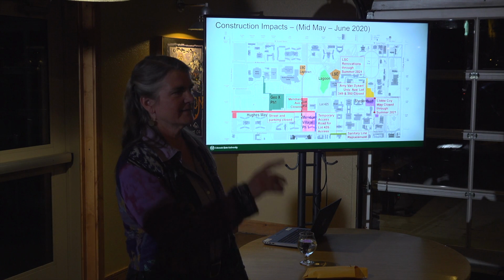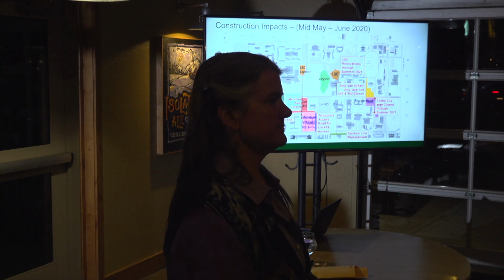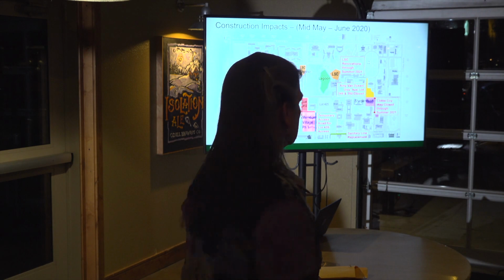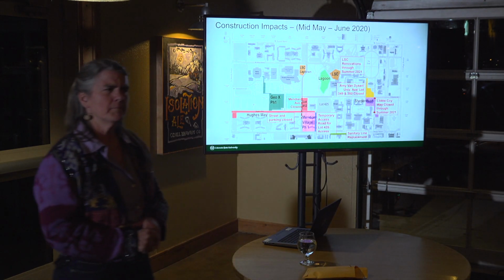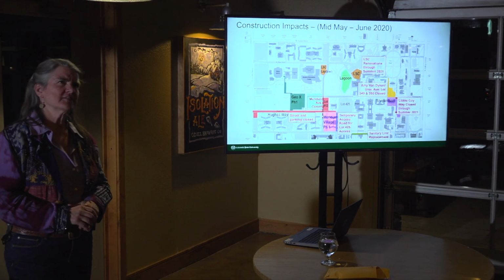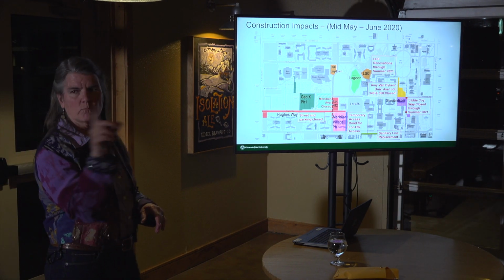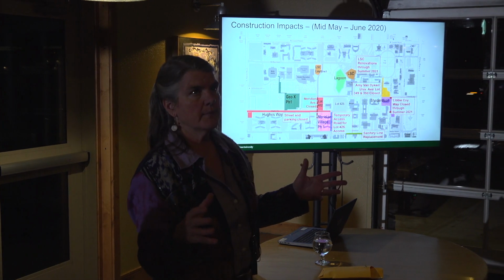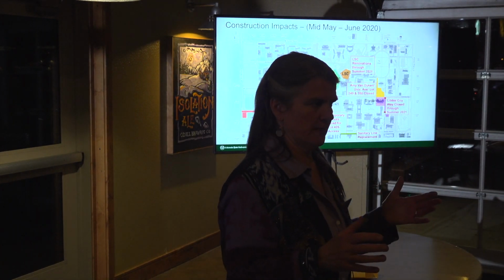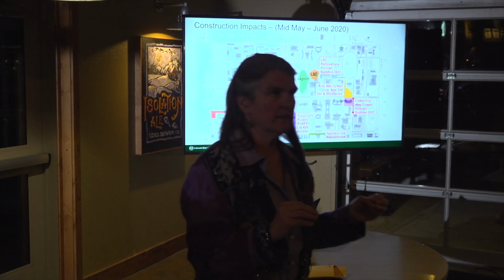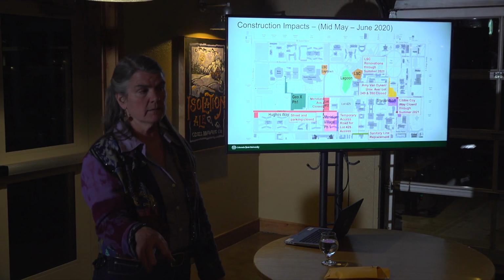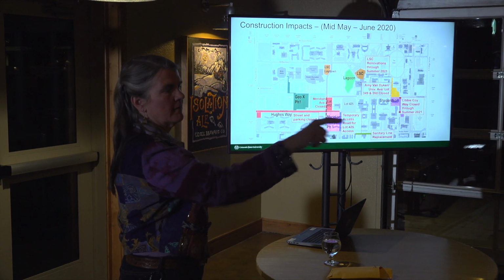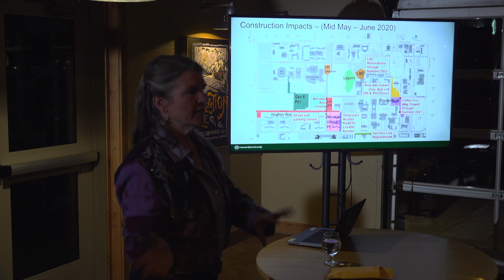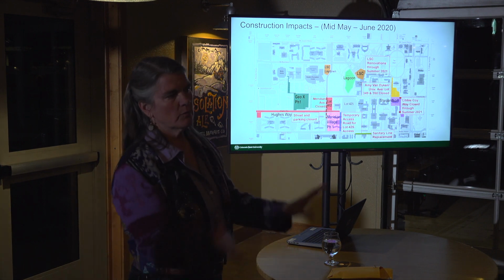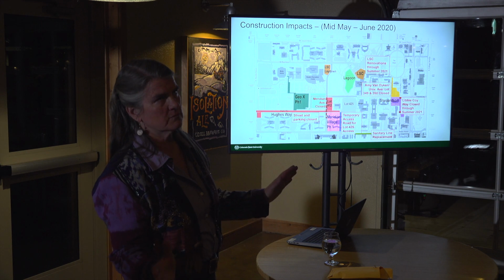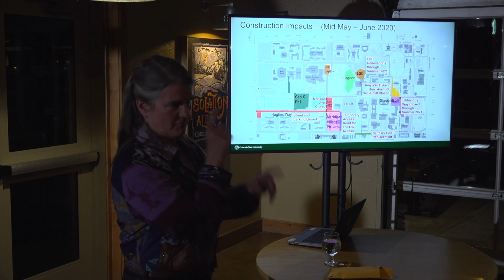Are you concerned at all about thermal creep of the field, with the warmer winters? That's a great question. Remember it's a heating-dominated load, so worried about thermal creep in the field - it is not a balanced load, but it's close to one. Technically we extract more heat out of the ground than we put into it, but exactly what you said, as the climate moves generally warmer, it will tend toward a better balance.